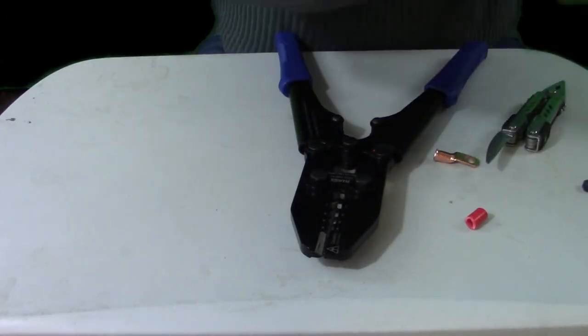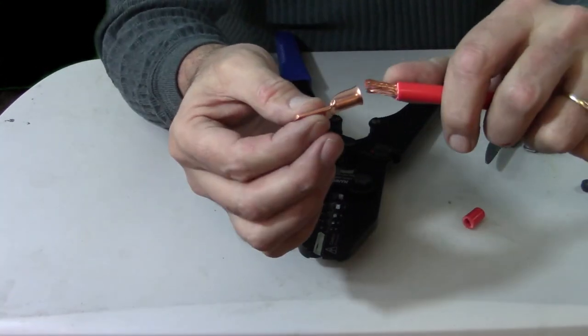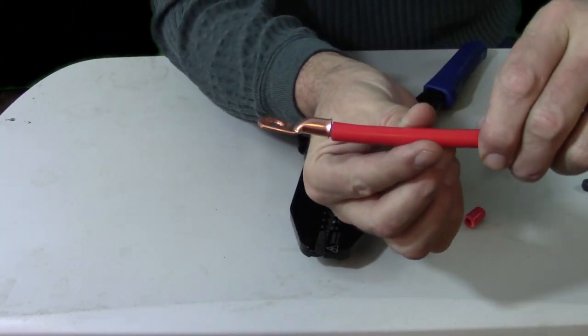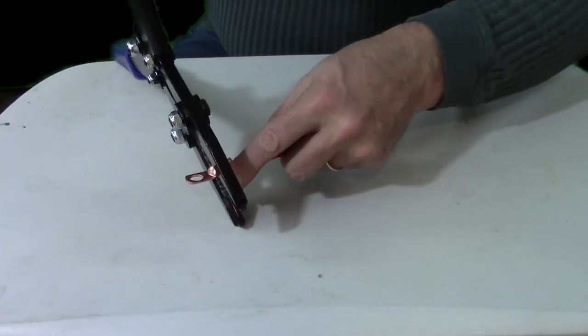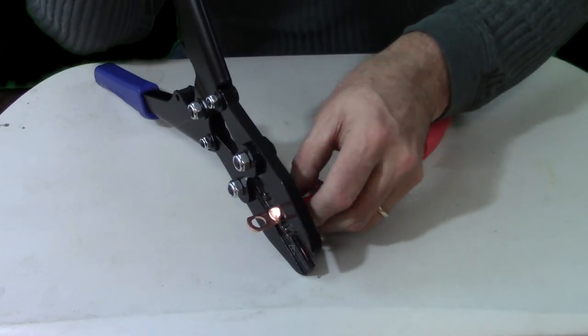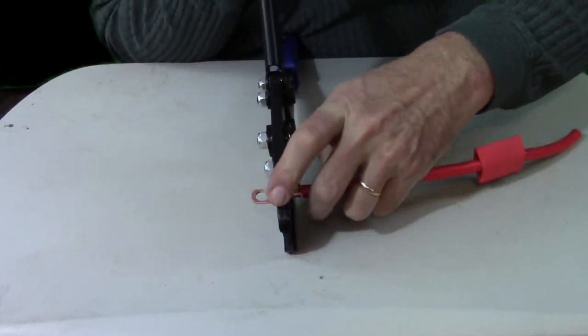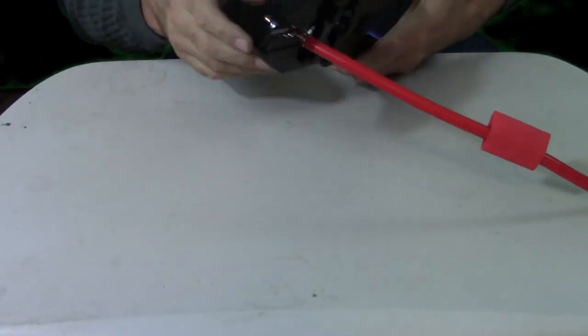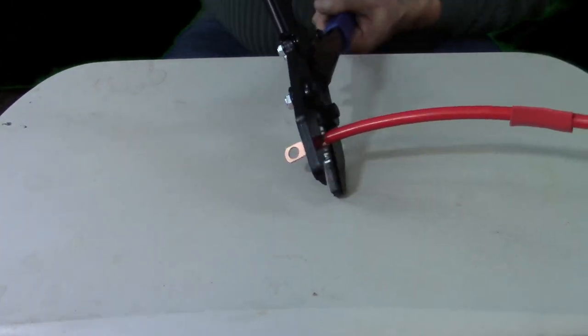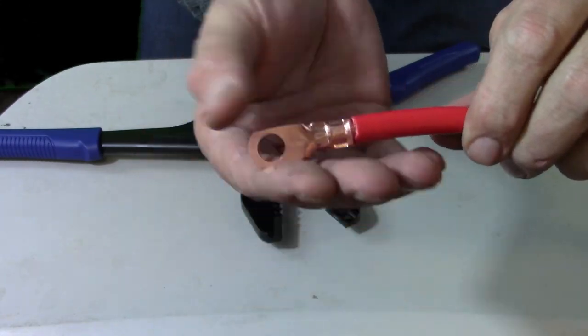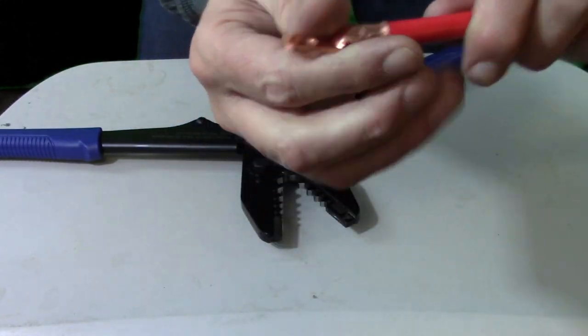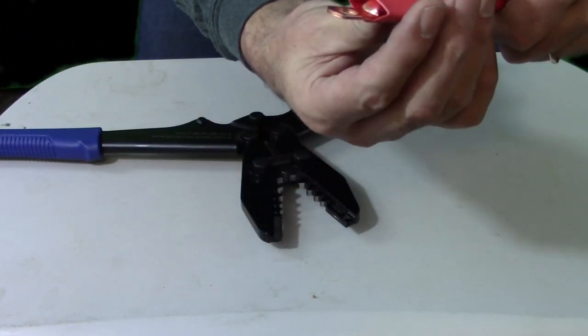Put it into the jaws of the crimper, crimp down a little bit and just kind of go back and forth on the wire. And the sheathing finishes breaking right off. Again, two crimps. Always want to start closest to the outside edge of the lug, closest to the end where the holes are, and then work your way towards the cable when you're crimping.